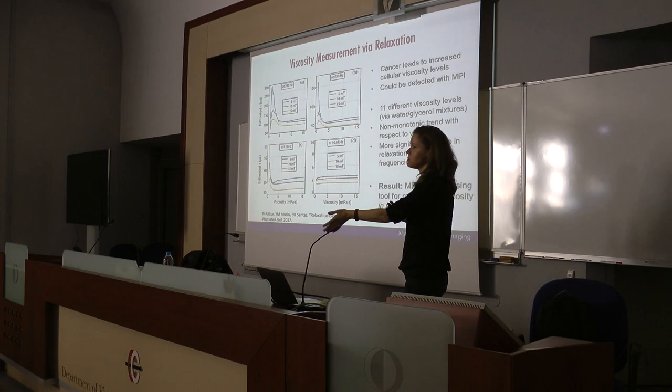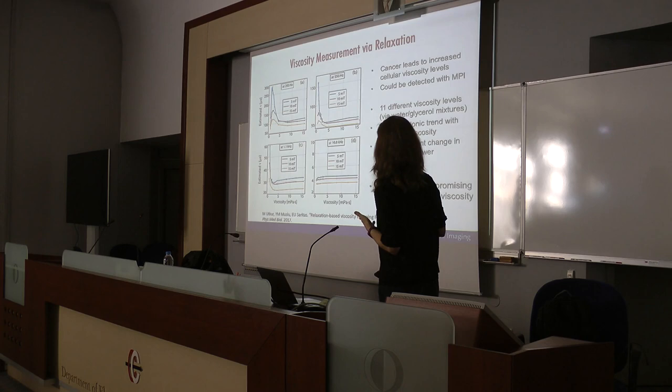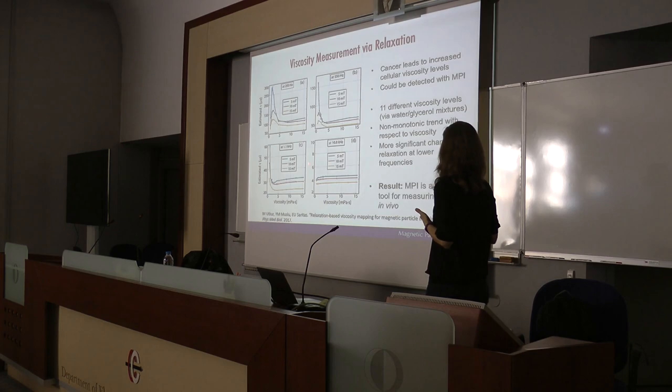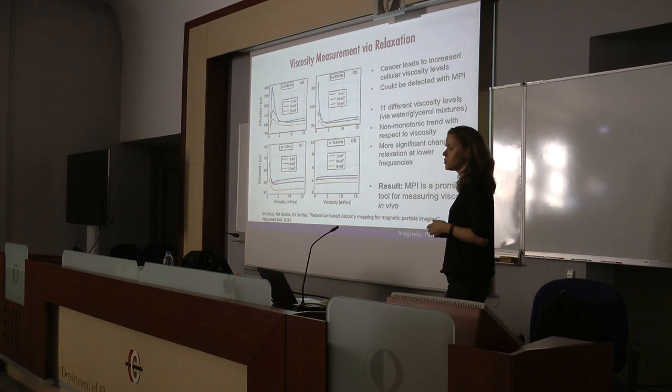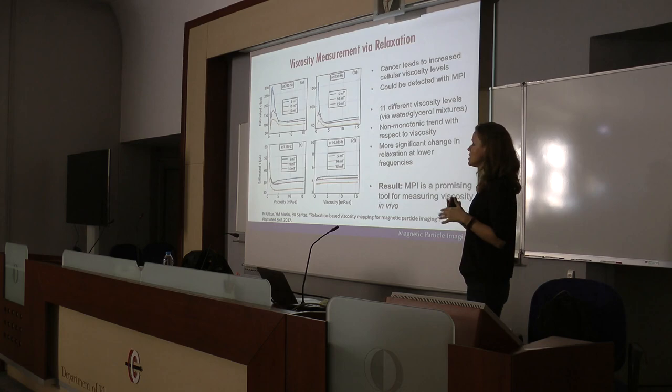We performed experiments on our MPS setup to show that with this time constant estimation technique, we could distinguish the viscosity of the environment the nanoparticles were placed in. The x-axis is the viscosity of the environment and the y-axis is the estimated time constant. We performed experiments at different frequencies and AC field amplitudes to find which frequency is most suitable for viscosity mapping in MPI. We found the best one-to-one mapping between viscosity and estimated time constant is achieved at around 1.1 kHz — notably far from the 20–25 kHz typical for current MPI systems, suggesting that moving to lower frequencies provides additional information from the nanoparticles.